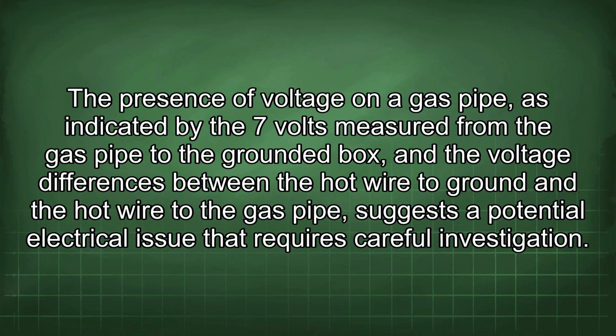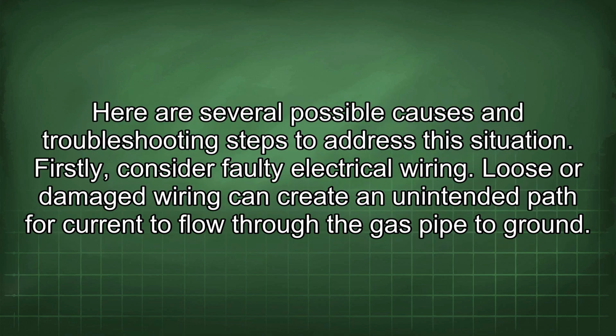Presence of voltage on a gas pipe, as indicated by the 7 volts measured from the gas pipe to the grounded box, and the voltage differences between the hot wire to ground and the hot wire to the gas pipe suggests a potential electrical issue that requires careful investigation. Here are several possible causes and troubleshooting steps to address this situation.